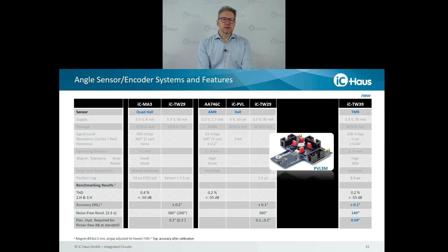Okay, regarding all my benchmarking results, I already have a summary here. We can expect hi-fi signals, meaning our harmonic distortion is well below -50 dB. I'd like to mention this as a precondition: when heading for high accuracy measurements, it's a precondition to have low harmonic distortion, otherwise we cannot reach our goal.